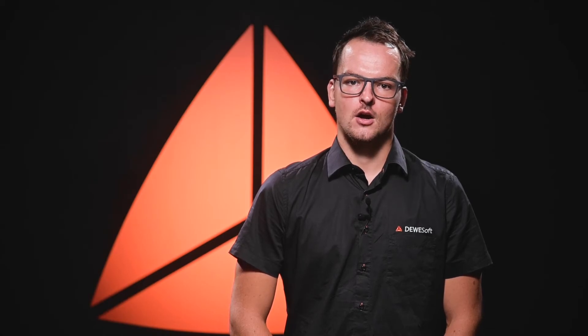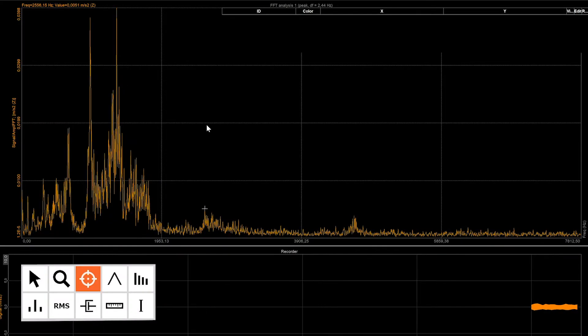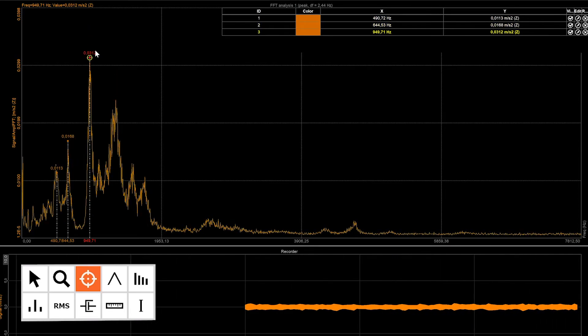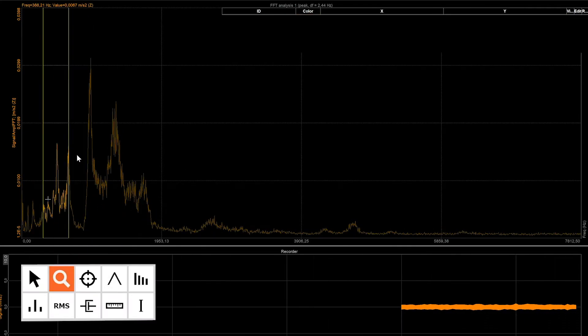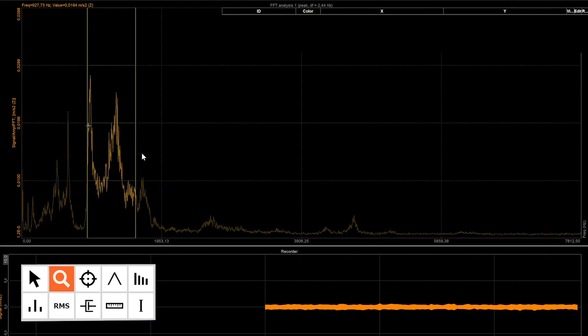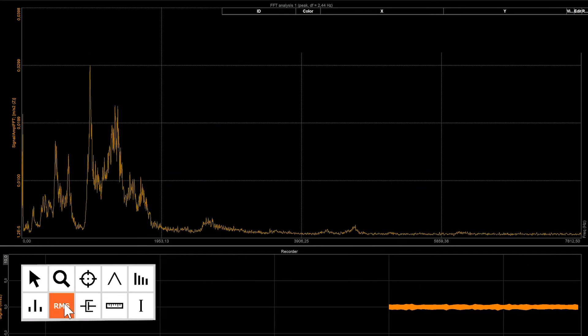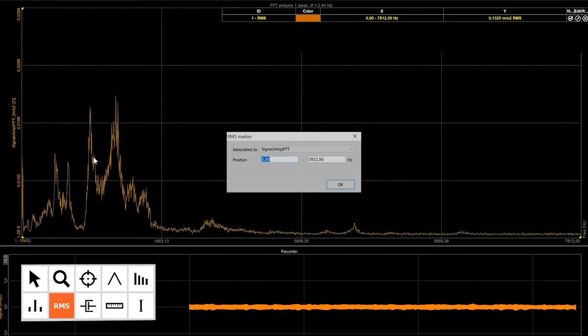For advanced analysis of recorded data, the Dewesoft FFT analyzer offers different kinds of cursors for automatic detection of the inspected phenomena. All cursors have an innovative interpolation technique allowing precise amplitude and frequency estimation. Free markers can be freely added to any position in the spectrum, showing the frequency and amplitude of the peak. With the zoom marker, you can easily zoom into the selected region of the spectrum for a more detailed view of the peak values. The RMS marker sums up all the FFT lines in the selected band and calculates the RMS value.